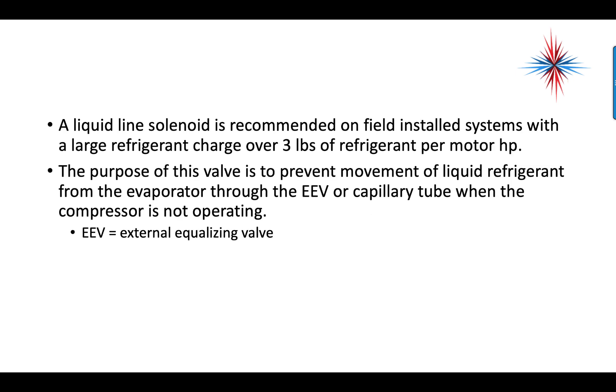A liquid line solenoid is recommended on field-installed systems with a large refrigerant charge — over 3 pounds of refrigerant per motor horsepower. The purpose of this valve is to prevent movement of liquid refrigerant from the evaporator through the EEV (electronic expansion valve) or cap tube when the compressor is not operating.